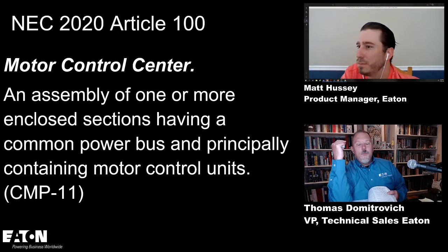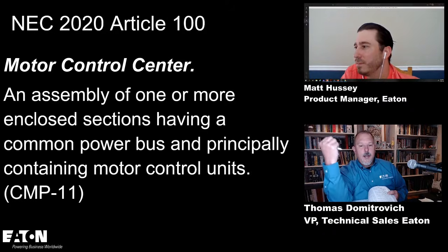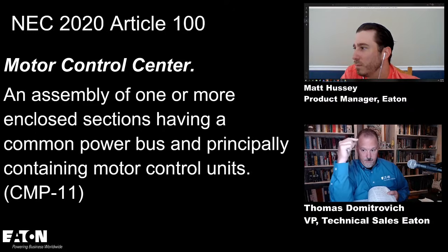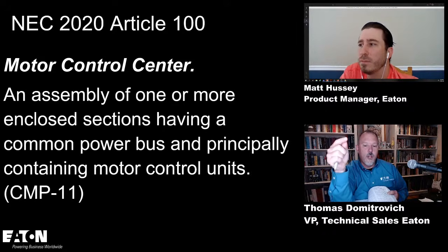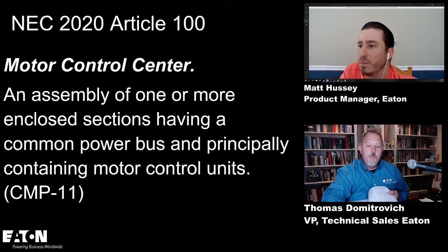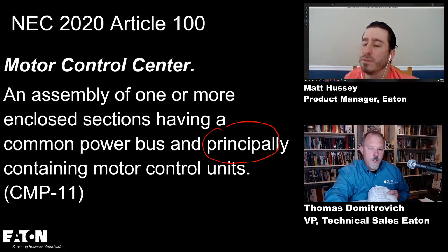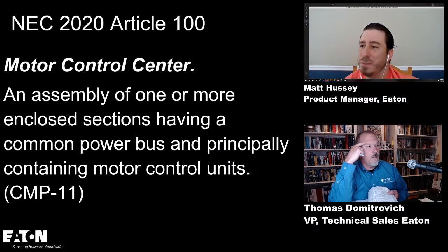Okay, now, to understand what a motor control center is, I went to the 2020 Code, Article 100, to the definition of motor control center, and it says an assembly of one or more enclosed sections having a common power bus and principally containing motor control units. Matt, do you have any idea why they said "principally containing motor control units"? I would expect that's because the majority of the units are motor control units. But there could also be distribution applications too. So you have branch feeders and whatnot.